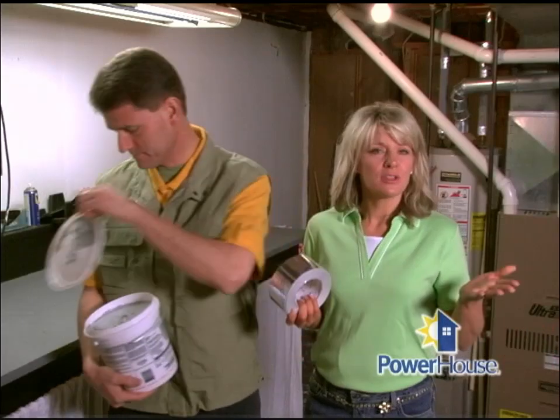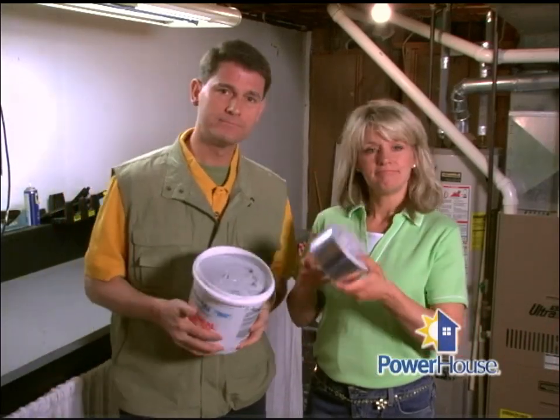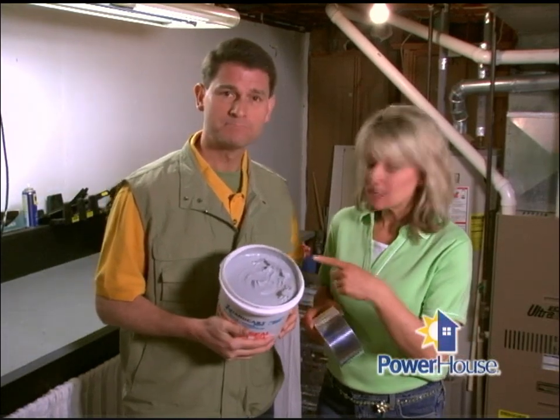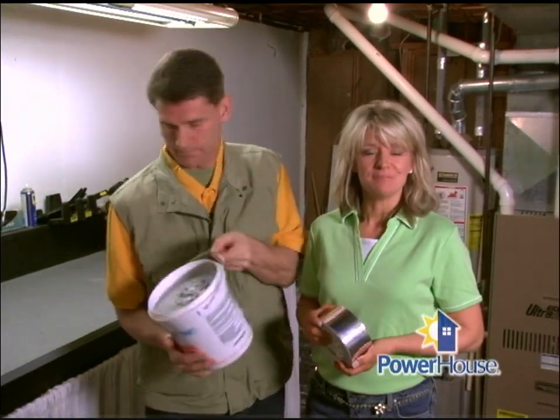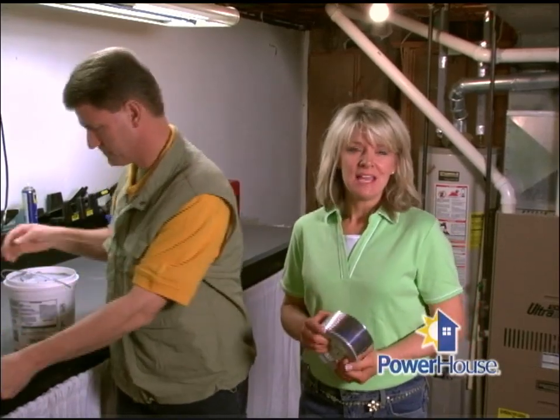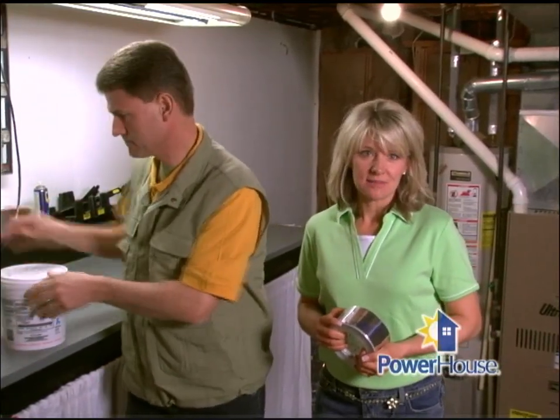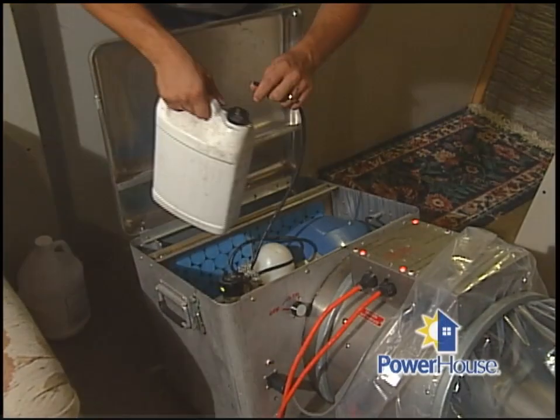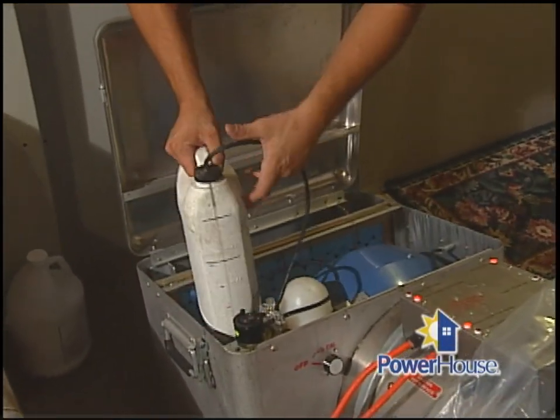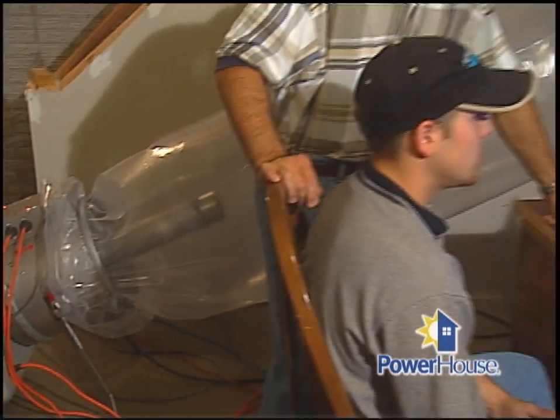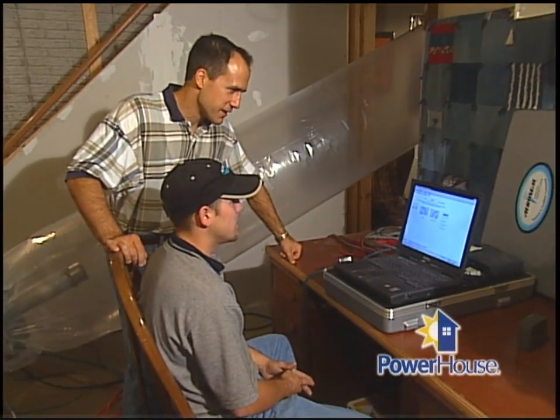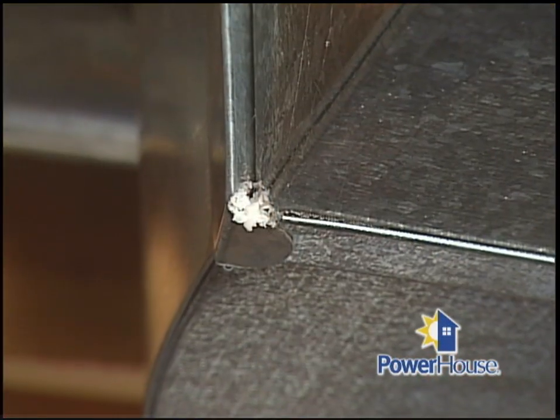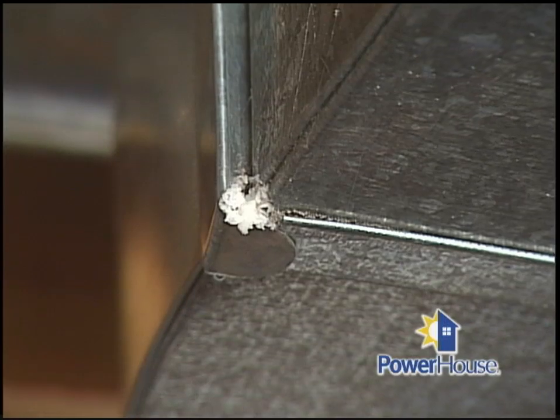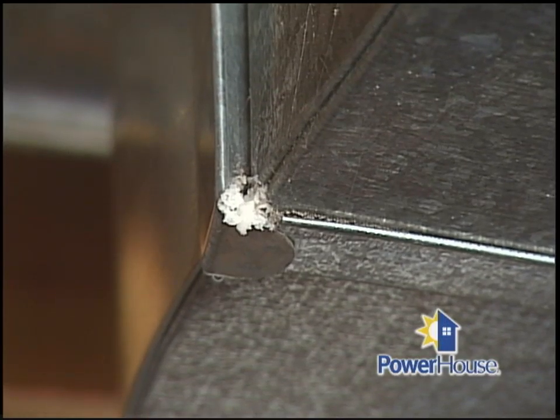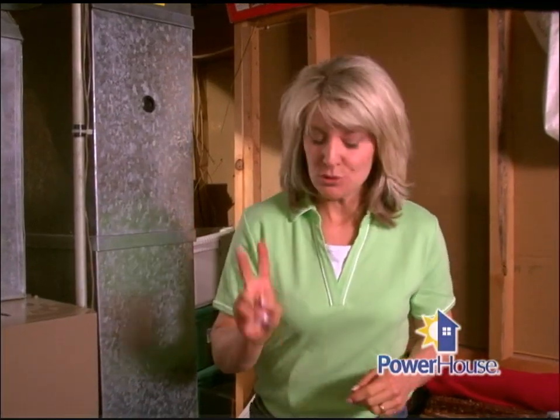Right. Now, basically, there are 3 ways to seal your ductwork. 2 of them, tape like this, and mastic, which is actually a type of caulk, can be installed by a do-it-yourselfer, and we'll show you how to apply these to your ductwork in a minute. The third method involves the use of aerosol sealants, and that must be done professionally. It's a technology that we featured on Powerhouse before. It internally seals leaks in air ducts by blowing a fog of tiny particles into the duct system. These particles, which are sticky, flow through the ducts until they reach a leak, and then they seal it. This system does the most thorough job because it can seal duct leaks in inaccessible areas like walls, floors, and ceilings.